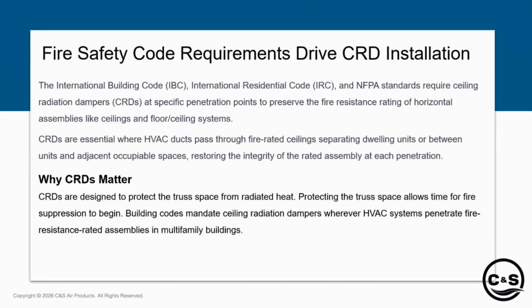So with that being said, the fire safety code requirements, the IBC and a couple other NFPA codes, all require ceiling radiation dampers to protect any kind of penetration points, making sure that the fire resistance rating is still applicable once you actually go through the ceiling deck.